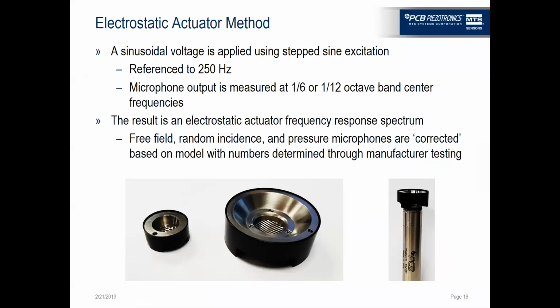So the interesting thing with this is, okay, I'm giving you a relative response of the electrostatic actuator, but relative to what? Well, remember, we calibrate our microphones with a calibration source of 250 hertz. So the frequency output of the electrostatic actuator at 250 hertz is set to 0, and then everything else is set with respect to that. So again, your free field, random incidence, and pressure response are corrected based on the model of microphone and previous testing. And you can see the pictures down below, a couple of electrostatic actuators, and an image of how the actuator is installed on a half-inch microphone. This large one here is a 1-inch electrostatic actuator for a 1-inch microphone.